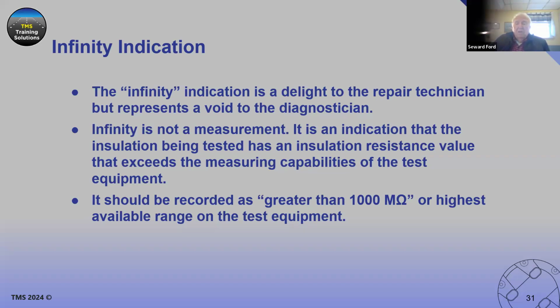What is your test equipment limit, the top limit for meggering circuits? If it's above that, state it's above 1,000 megohms. If it's 500 megohms, state it's above 500 megohms. We need that piece of information because we have to know when we start getting back into the areas that we can measure again. We've got to go timing on that and when we did it. Questions on that, comments? Sure, that information came from a Biddle Megger manual. There's a lot of good information you can get from their website as well.